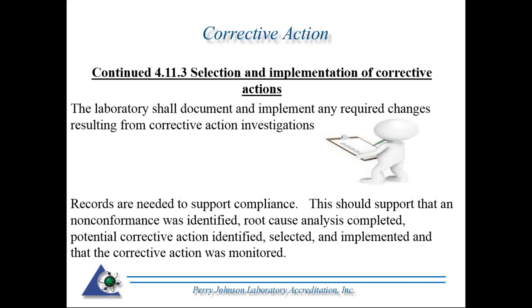Continuing with selection and implementation of corrective action, 4.11.3, the laboratory shall document and implement any required changes resulting from corrective action investigation. Hence, we're looking for records. As an assessor, or even you as a laboratory, if you're the quality manager or you're doing an internal audit, any corrective action needs to be supported by a record. Records are needed to support the compliance. The record should support that a nonconformance was identified, root cause analysis was completed, potential corrective action identified, selected, and implemented, and, as you'll see in a little bit, that corrective action was monitored.